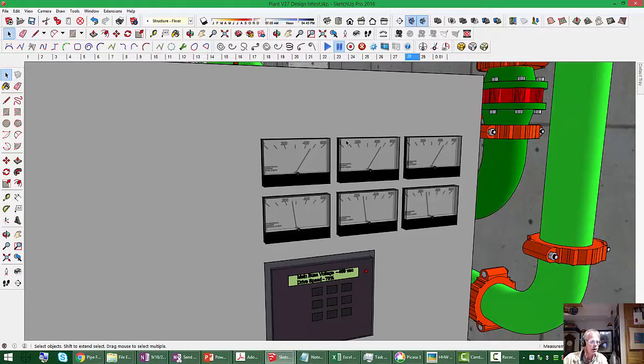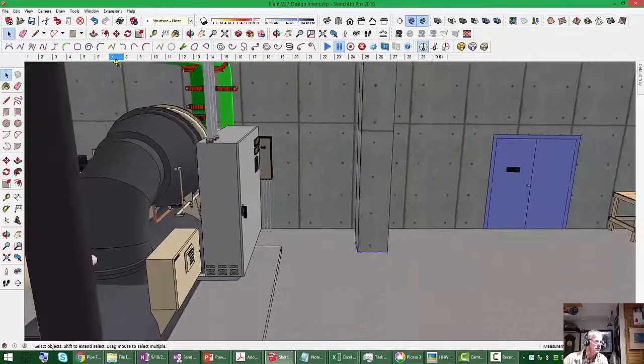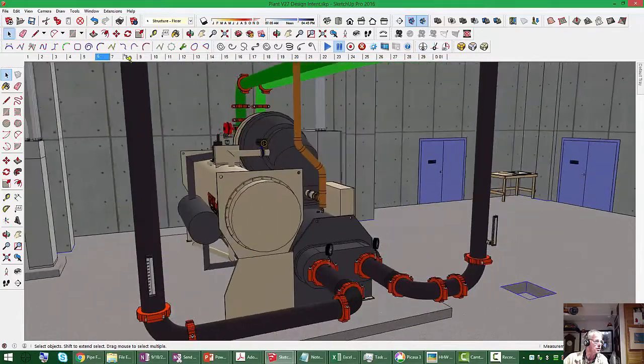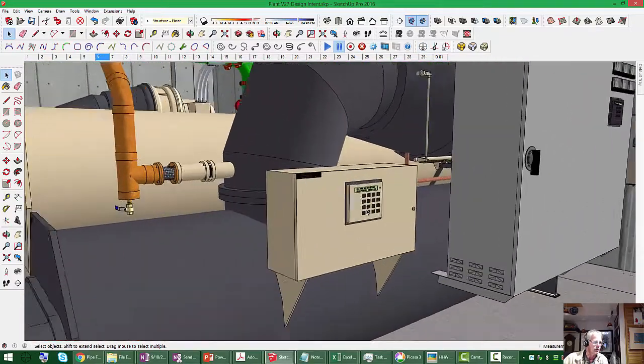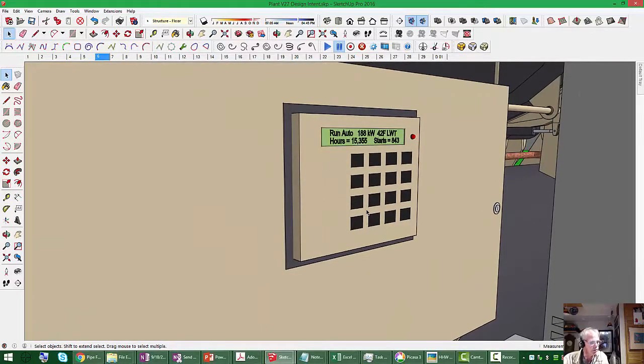And so, 188 kW. One thing you could do is say, well, in round numbers, just based on my experience in this industry, a fairly current technology machine might be at a half a kW per ton or better. Okay, so if this was a half a kW per ton machine, 188 kW in round numbers would be about twice that many tons. So 188 times 2 would be 360 tons.